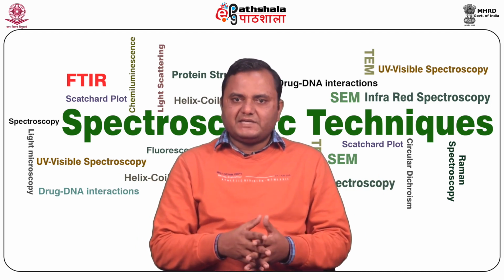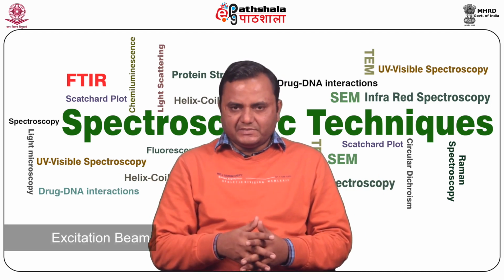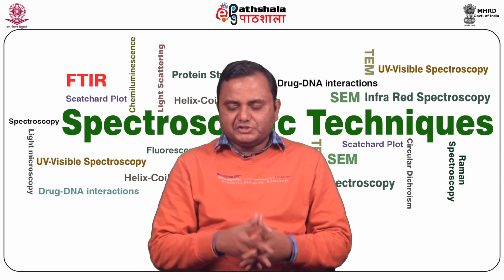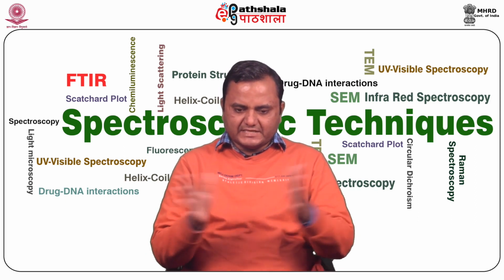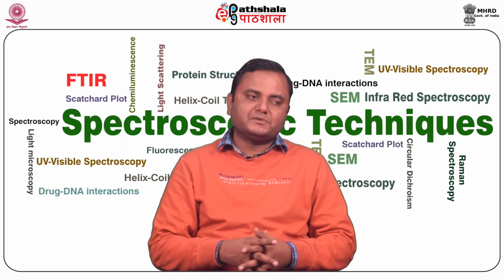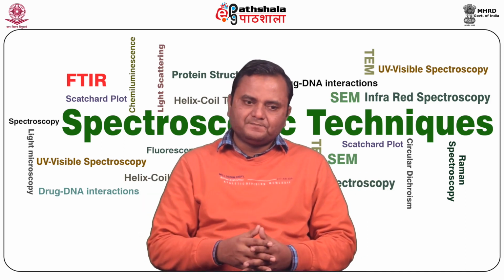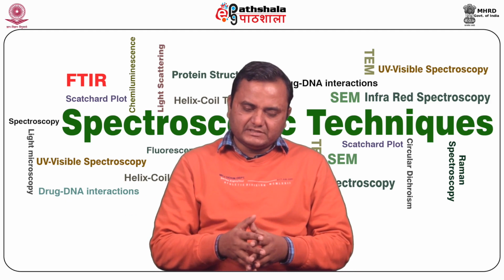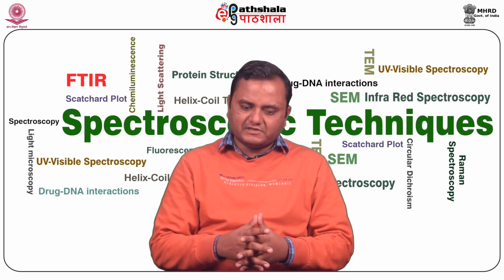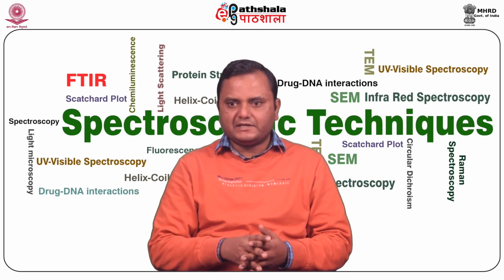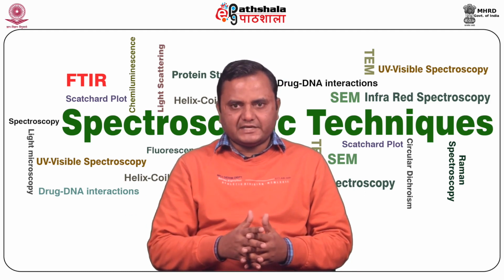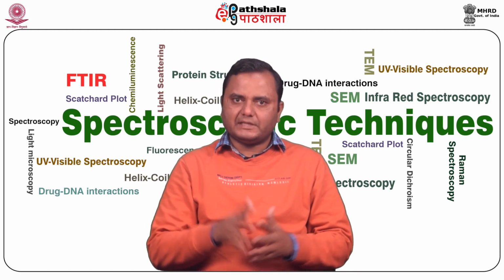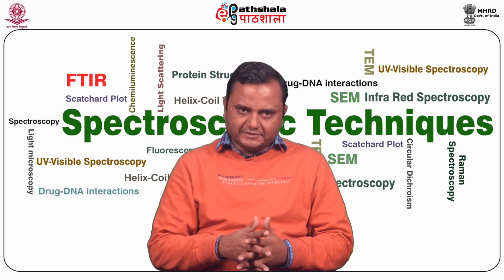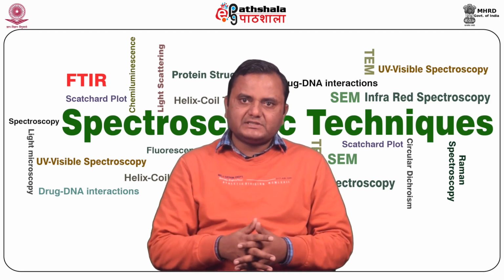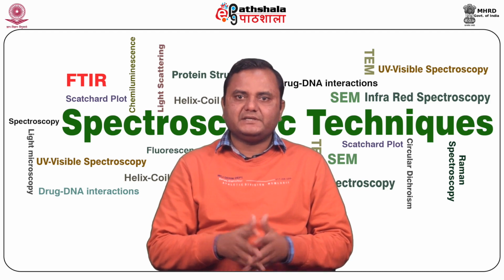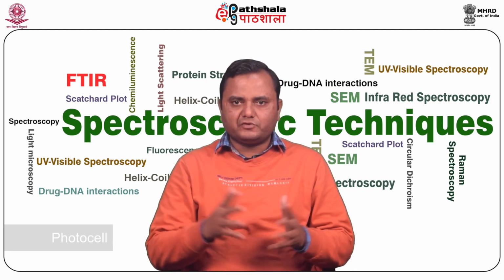And the detector is placed at 90 degrees to the excitation beam, because emission takes place in all directions, as compared to absorption, which always happens in a unidirectional linear direction. However, the emission takes place in all directions. That is why, to avoid any absorption phenomena, detectors are always placed at a right angle to the excitation light. So upon excitation, the sample molecule fluoresces and emits in all directions and is detected by a photocell at a right angle to the excitation beam.